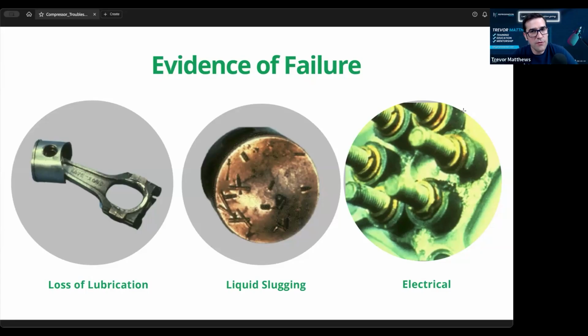And I like what you brought up before: when you're checking your superheat or starting up your system, you've got to check what your amps are, and make sure that your amps are in range. What are some of the tips you give technicians when they're looking at that? We need your run load amps, your full load amp draw. It's always going to be when the box or room is at its highest temperature. In other words, when you start it up, you shouldn't be running full load amp draw if your room is down to temperature, your box is down to temperature. You should be way off the full load amp draw there. Yeah.